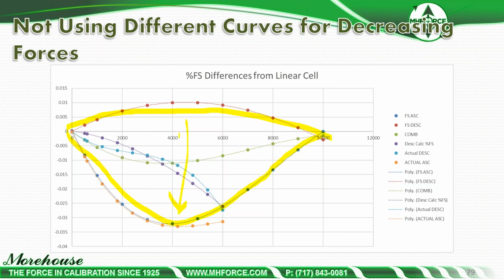And the combined curve, I know this is foreign to some, really takes all this information. The problem with the combined curve is you have that much uncertainty, right? By taking all the information and plotting it, your uncertainty gets a lot larger. But any point you do within that large span will be in. What's going on here is saying, hey, if I load it to 60% and come back, here's a curve. If I load it to this, here's a curve. So they're trying to classify things a bit differently. And in fact, in this one, here's the combined. But that green kind of splits where you're going to load it.